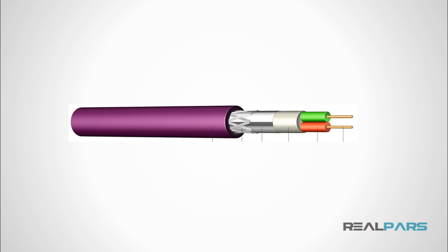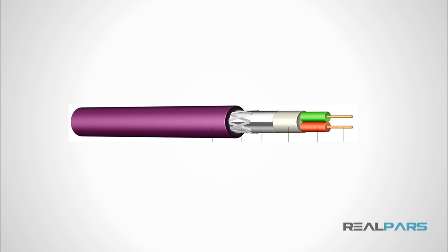The Profibus cable is a shielded twisted pair. We describe the outside as the outer sheath, followed by a braided shield, a foil shield, an inner sheath, and two single core wires, one green and one red.